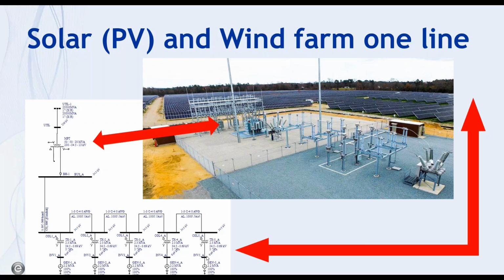And from the generator, I have a pad mount transformer. Some people call it a GSU as well, to go up to the collector system level from usually 0.69 kV to 34.5 kV. At 34.5 kV, I will use my collector system to connect each of the inverters together radially. You can see from this design, the farthest is collector 5A, and it would go through the collector system all the way back to the low end of the main power transformer. Some people call this main power transformer the substation transformer or the utility transformer, depending on the nomenclature. That's basically the one-line design of a solar farm, or a wind farm if you replace the inverter generator with Type 3 wind turbines.